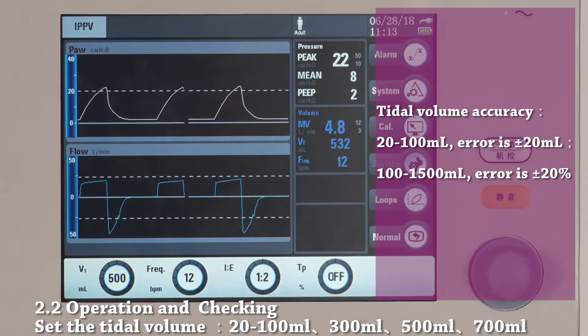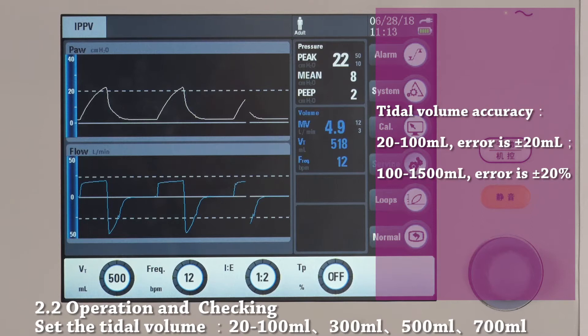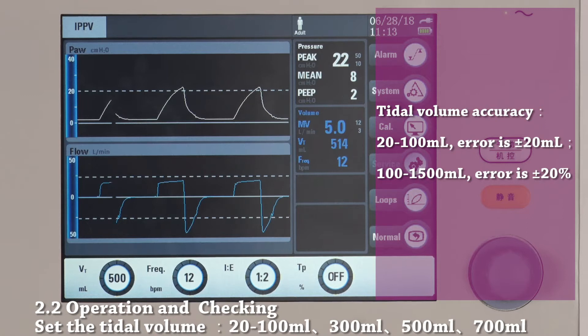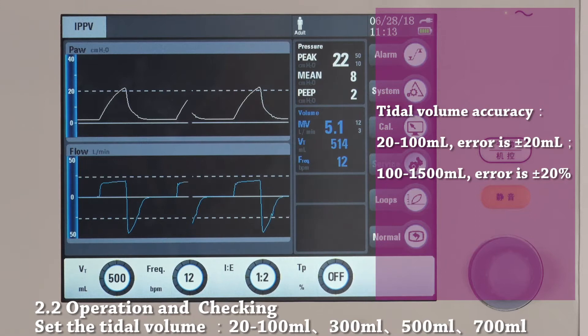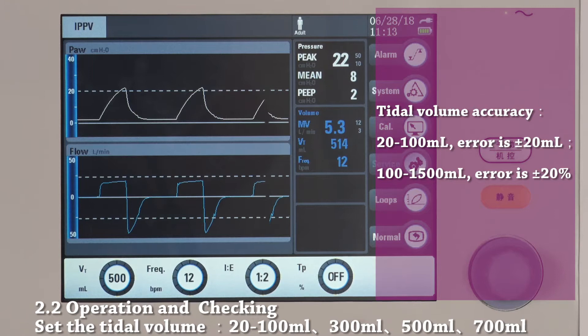If the tidal volume is out of range, it is necessary to perform calibration of the flow sensor. In the later parts, we will demonstrate how to do it. Please, for different values of tidal volume, check the accuracy. We suggest you try for 300 ml, 500 ml, and 700 ml.